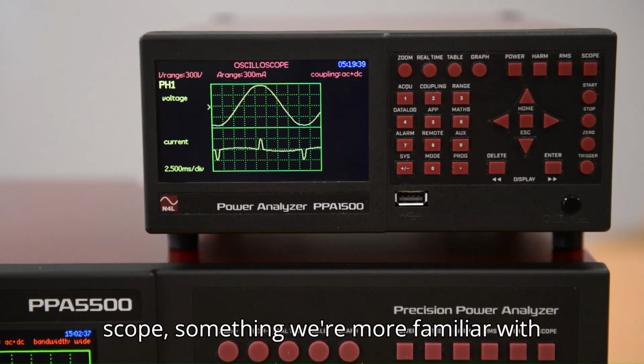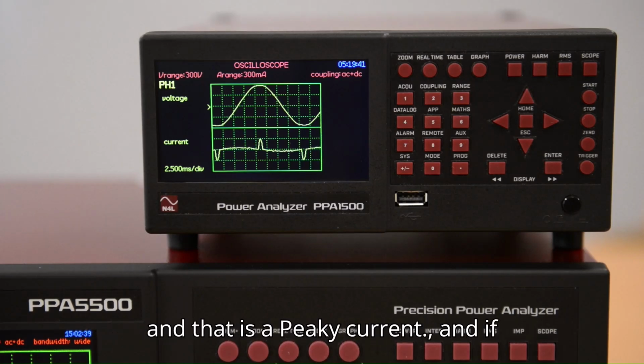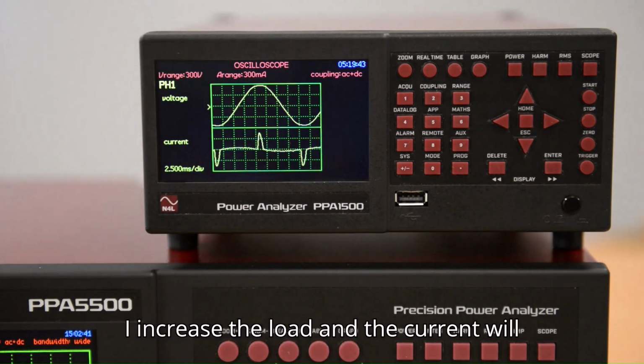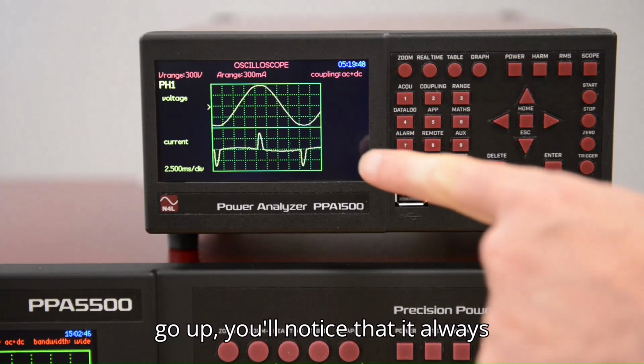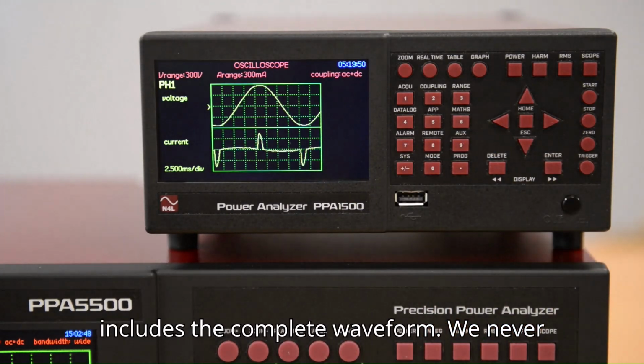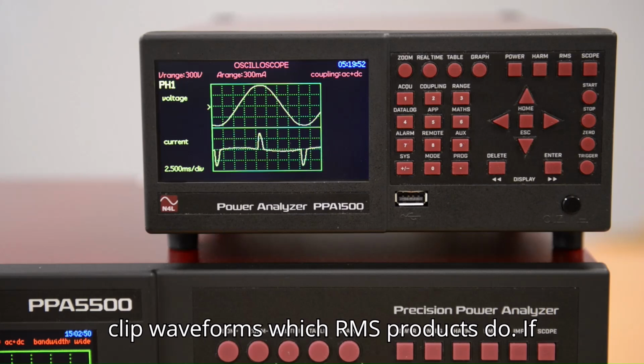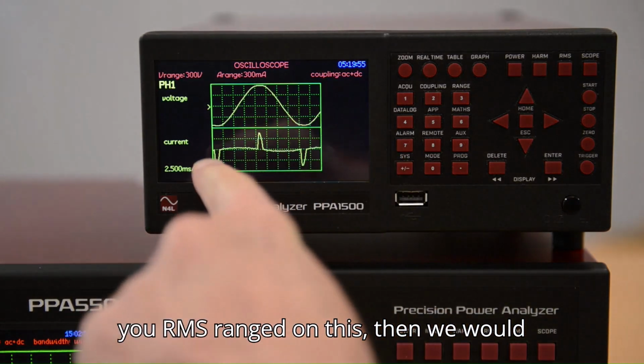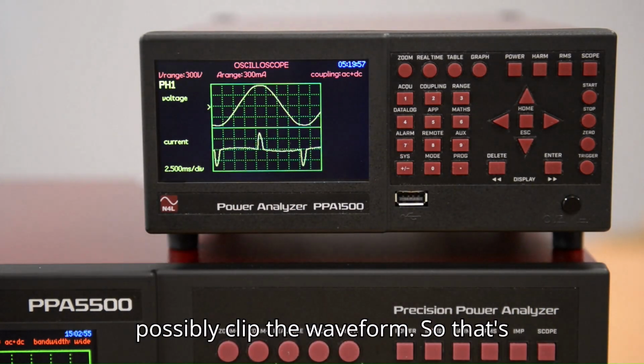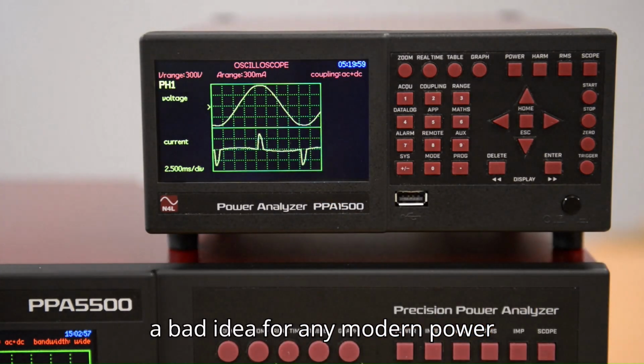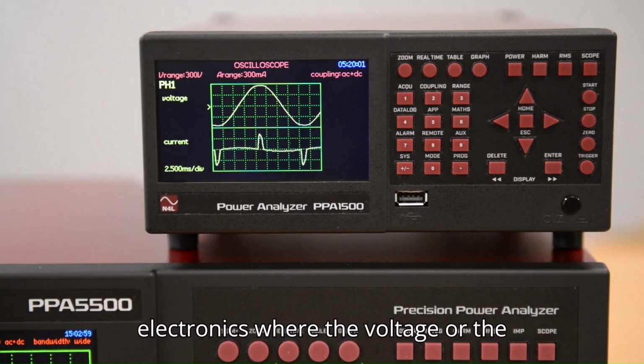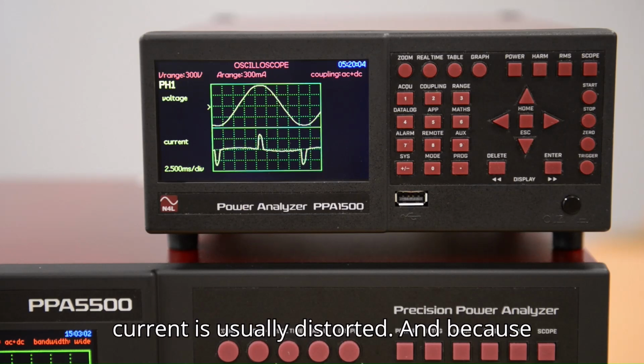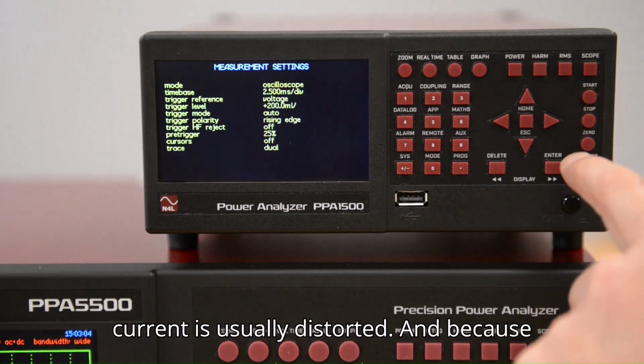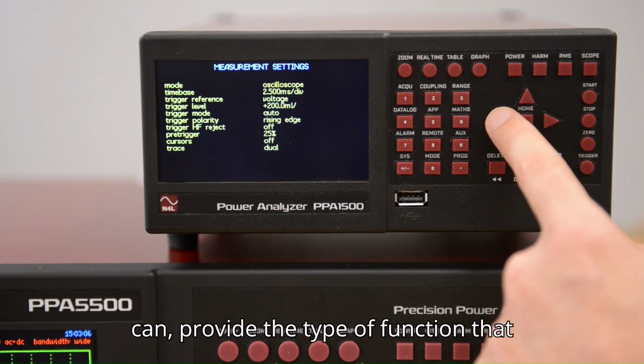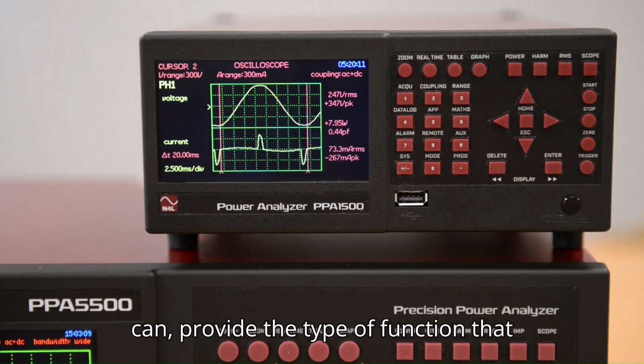We're seeing what we're familiar with, and that is a peaky current, and if I increase the load, then the current will go up. You'll notice that it always includes a complete waveform. We never clip waveform, which RMS products do. If you're RMS ranged on this, then we would possibly clip the waveform. So that's a bad idea for any modern power electronics, where the voltage or the current is usually distorted. And because people like oscilloscope functions, we can provide the type of function that people expect.